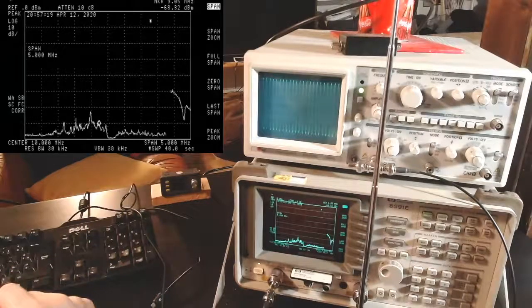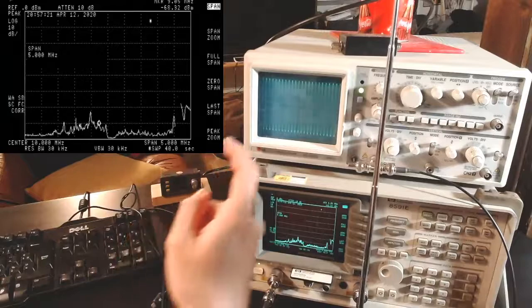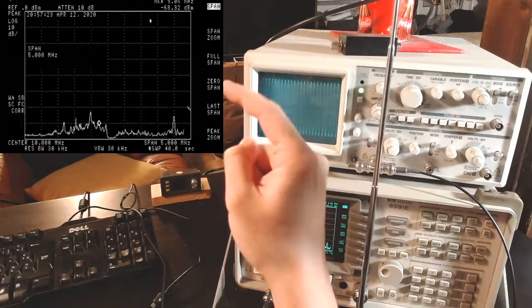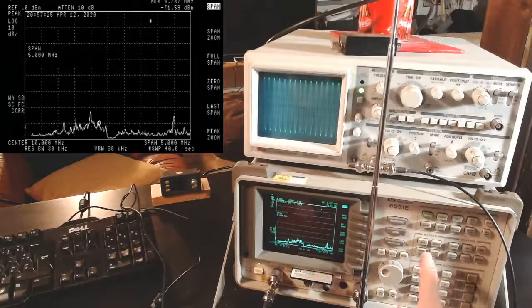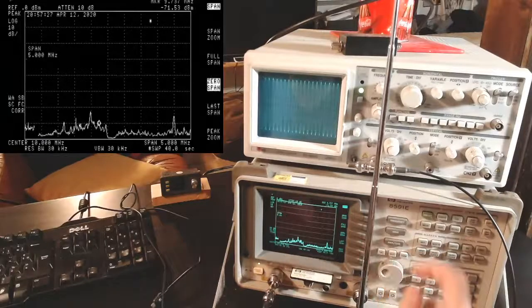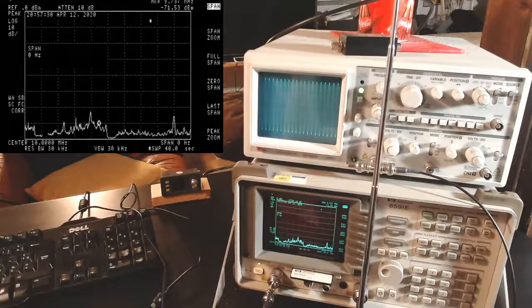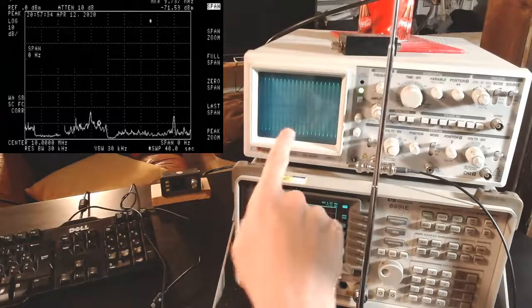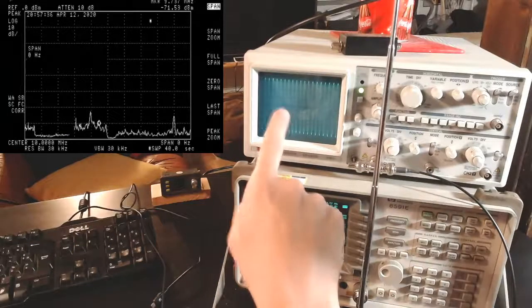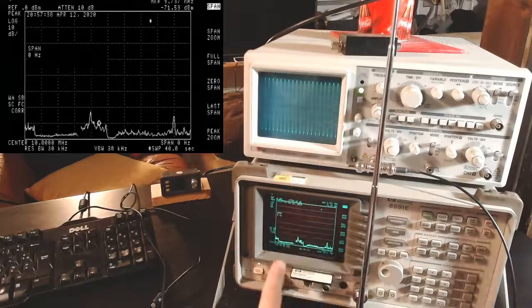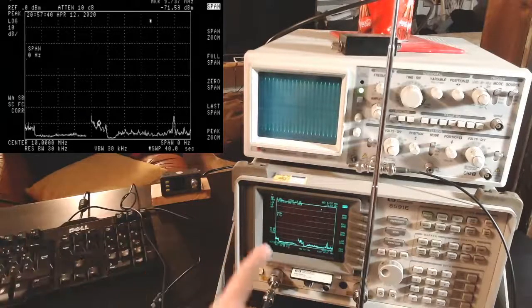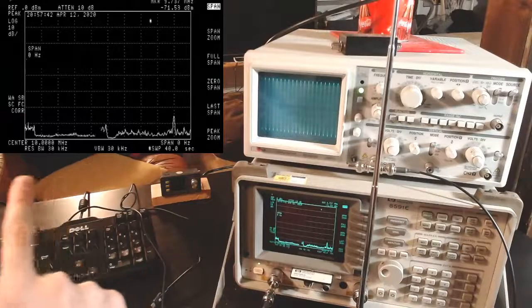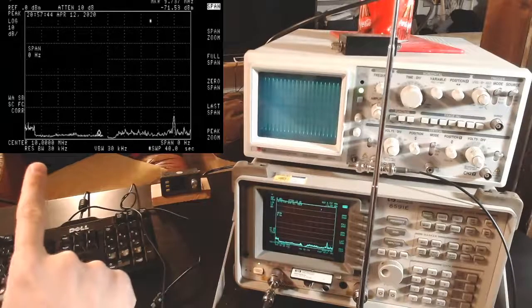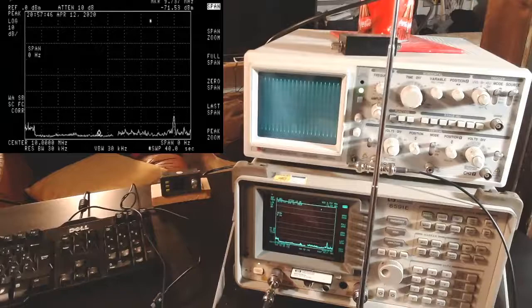This is a functionality of the spectrum analyzer. It's available here, and so I'm going to click it now. Zero span. When zero span is set, the tracking generator will always output the frequency at the center frequency. So now the tracking generator is outputting a constant frequency at 10 megahertz at minus 5 dBm.